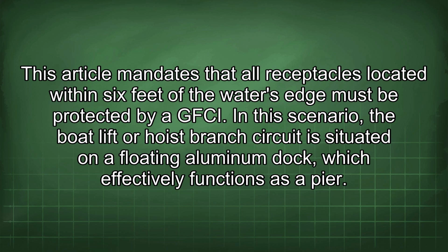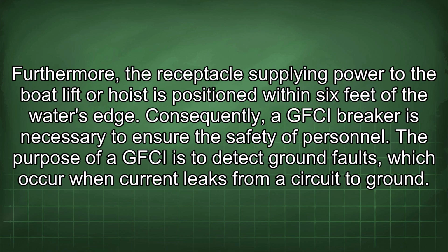In this scenario, the boat lift or hoist branch circuit is situated on a floating aluminum dock, which effectively functions as a pier. Furthermore, the receptacle supplying power to the boat lift or hoist is positioned within 6 feet of the water's edge. Consequently, a GFCI breaker is necessary to ensure the safety of personnel.